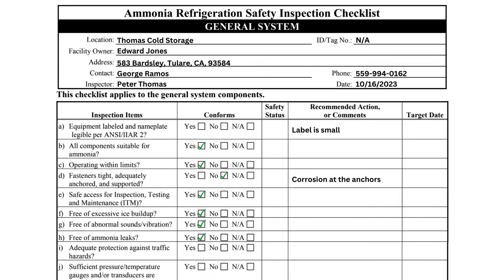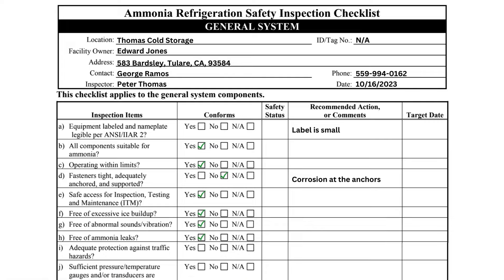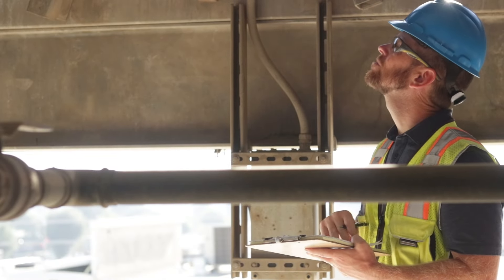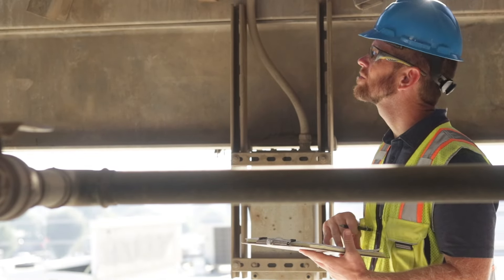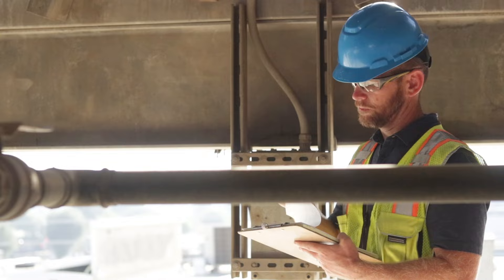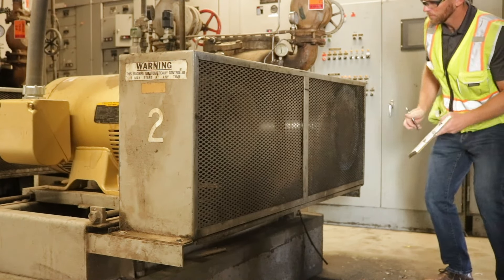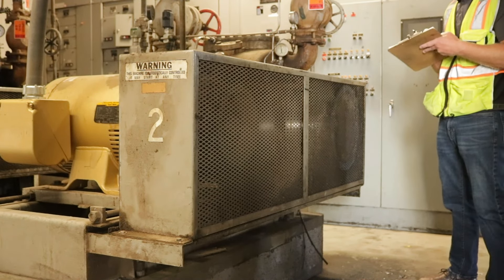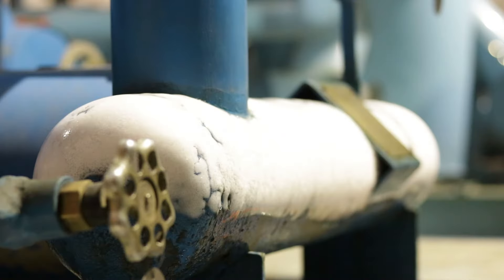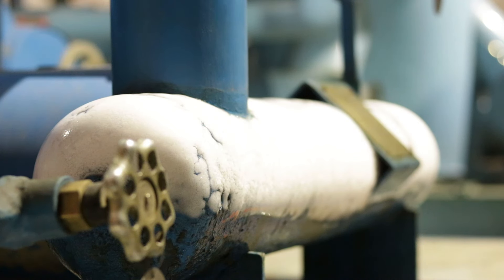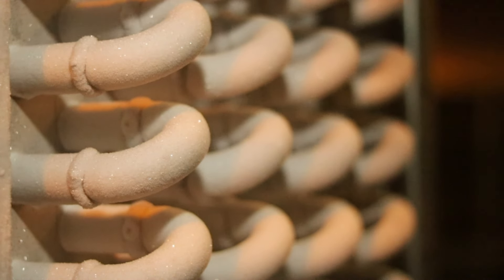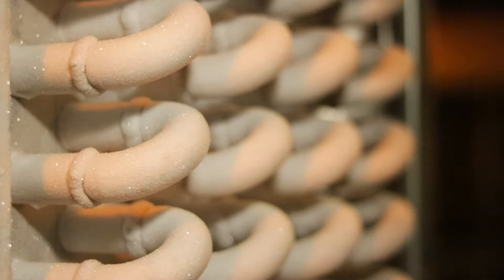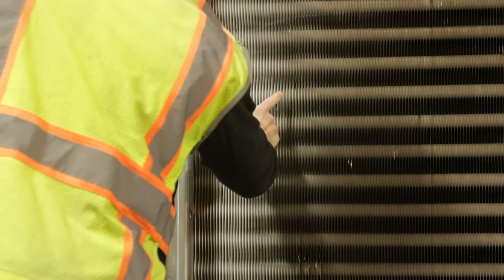Checklist items F, G, and H are specific to leaks and other equipment deficiencies. The inspector must do a visual inspection of each piece of equipment in the system to verify the equipment is free from vibration and leaks. Item F directs the inspector to check for ice buildup, which is possible to see on the low side of the system. Ice buildup is particularly relevant to air cooling evaporators.